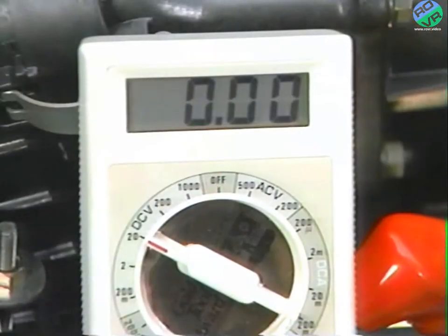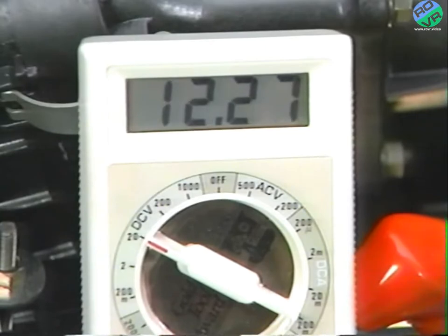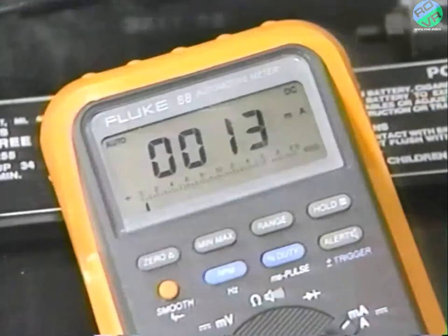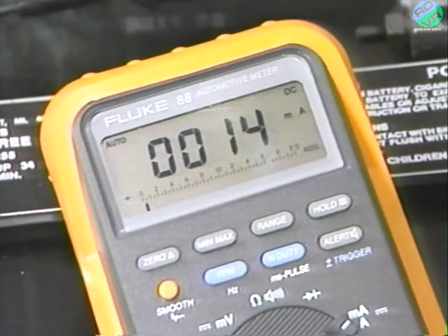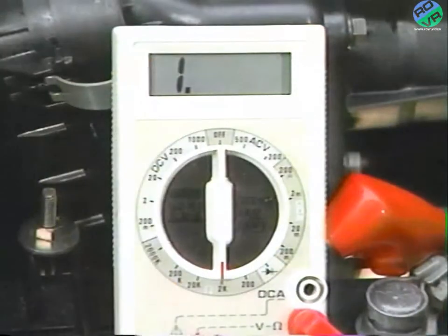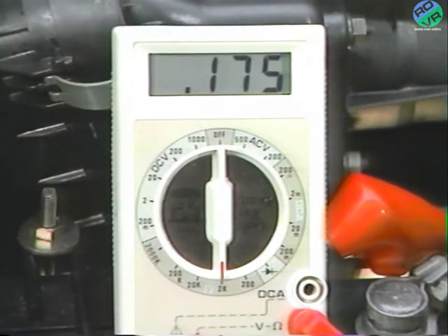Test instruments for electrical circuits include the voltmeter, ammeter, and ohm meter. A voltmeter checks the electrical pressure or voltage when connected in parallel with the circuit. An ammeter measures the flow of current when connected in series with the circuit. An ohm meter checks the resistance of the circuit in ohms when there is no current flowing through the circuit.